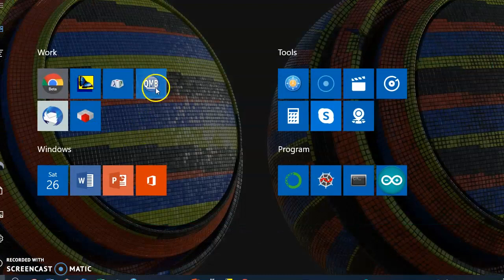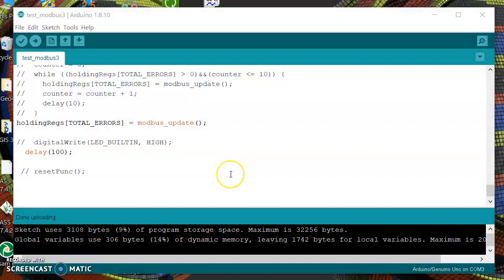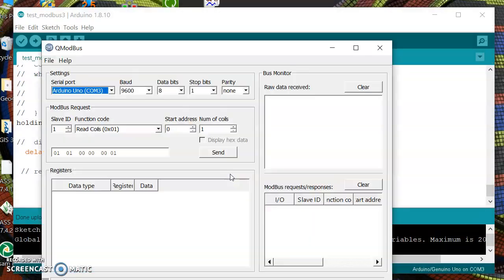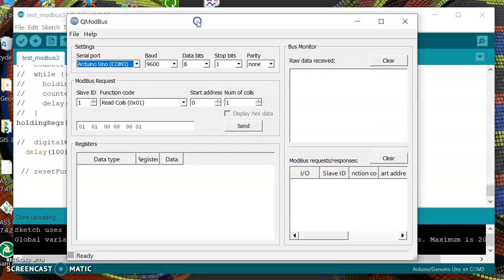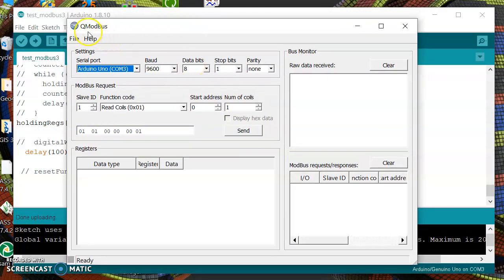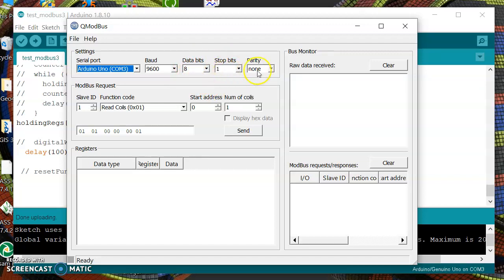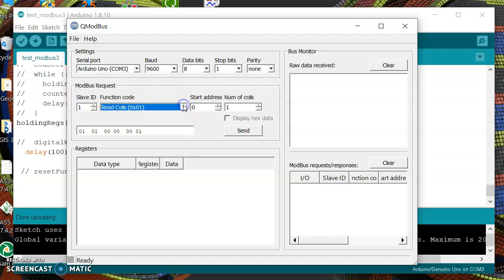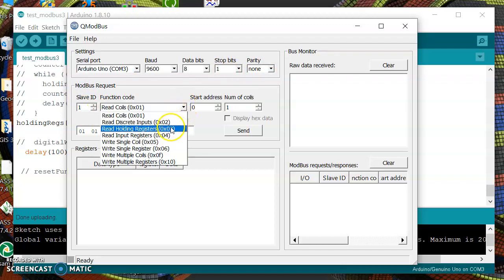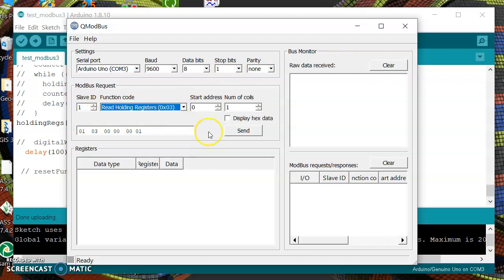Now we are going to use the tool Q Modbus. COM3, 9600 bits per second, number of data stop bits 1, no parity. The slave is 1 and we are going to use function number 3.